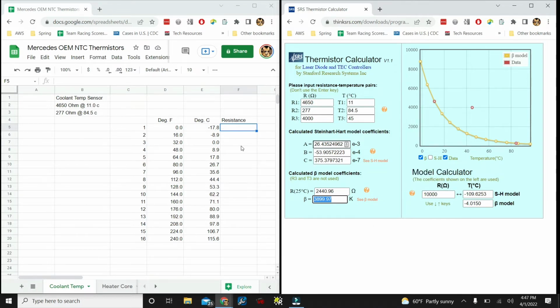All we have to do is start entering values from our table here, which we've got negative 17.8 degrees C. We're going to type that in here, and when we hit enter, it gives us a calculated resistance. We're going to type that value over here, rounding to the nearest ohm—we don't need decimal points—so it's going to be 21,864.